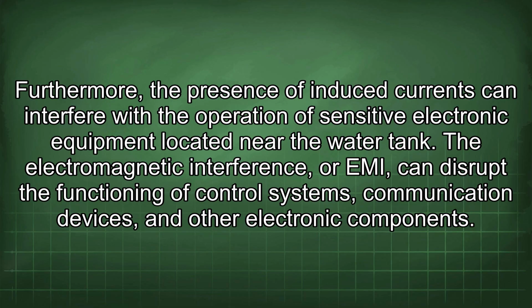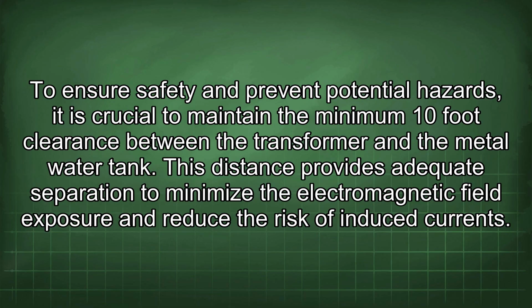Furthermore, the presence of induced currents can interfere with the operation of sensitive electronic equipment located near the water tank. The electromagnetic interference, or EMI, can disrupt the functioning of control systems, communication devices, and other electronic components. To ensure safety and prevent potential hazards, it is crucial to maintain the minimum 10-foot clearance between the transformer and the metal water tank.